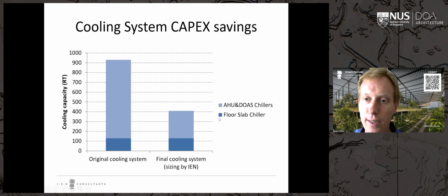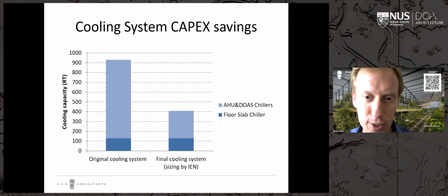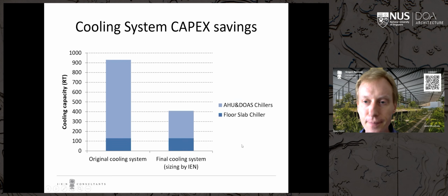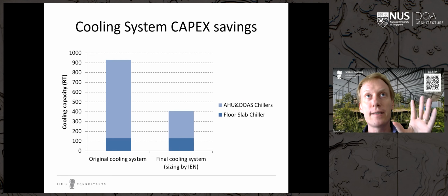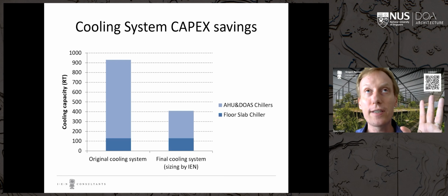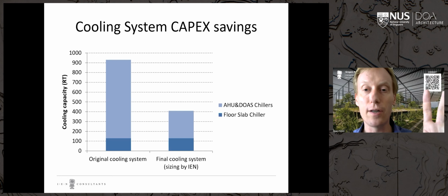We also had this split cooling system where about a third of the cooling came from slab cooling. But the mechanical engineer, although he had some calculation software, couldn't really incorporate that into it, so he was uncertain whether it was correctly simulated. Another thing he couldn't simulate was the thermal stratification of the space - the fact that under the skylights of the factory there would be hot air just sitting there, not mixing with the aircon zone.